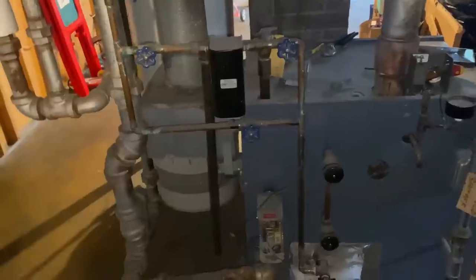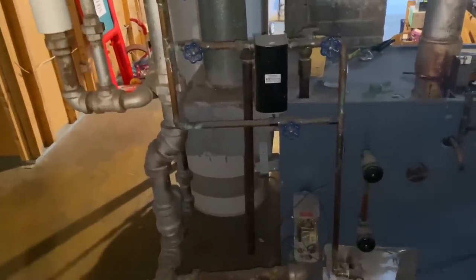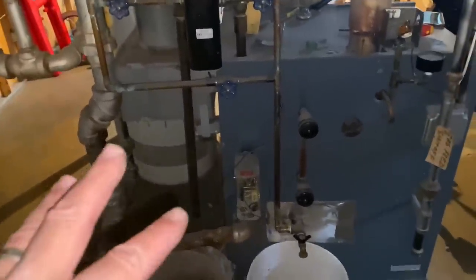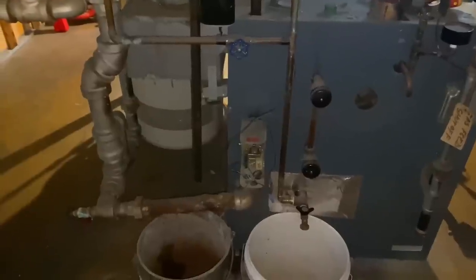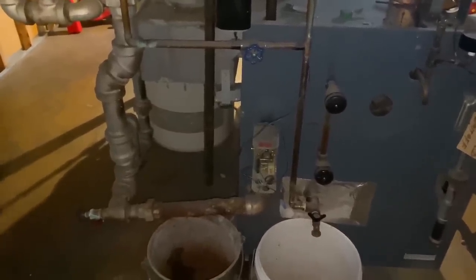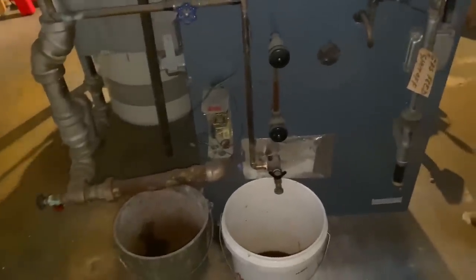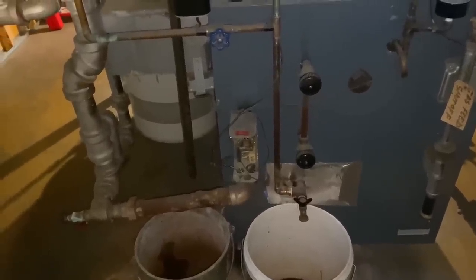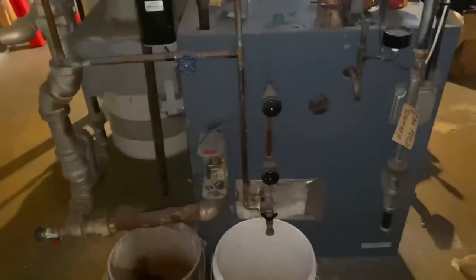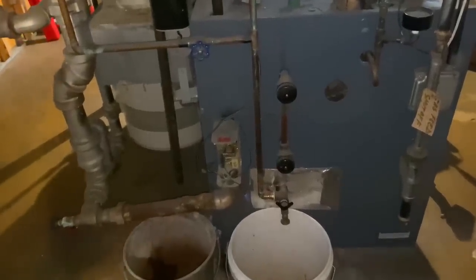That means you're going to need to replace the boiler. It's working today - it's been leaking for a while, but we haven't even pulled the burners out yet to look inside. When we first got here, Peter actually went to the wrong thermostat. There's a Honeywell T87F round thermostat with the mercury - we bypassed it. Then I went upstairs and took the plate off and there was no wire on the heating circuit. We were at the wrong thermostat. Then I looked around and right behind us was the other one.